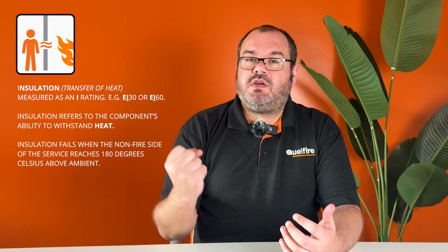The second aspect is insulation, and this is the one that causes a lot of confusion. So I'm going to discuss what it is, and then I'm going to go over just the difference between the two. So insulation, we're talking about that from a fire resistance perspective, is the ability or the fire resistance of the seal and the wall or the floor to stop that heat transfer from the fire side to the non-fire side.